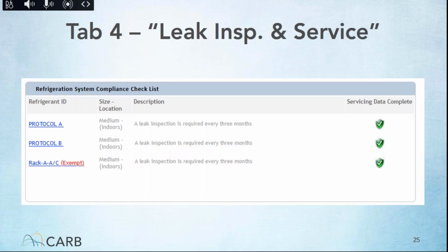So the analysis we take on the leak inspections is, I know my predecessors have tried to do this plus or minus X number of days. The rule doesn't really provide for anything like that. The rule just states 3 months. It doesn't specify what the full integer is. So we look at it more as, if it's 3.5 months, we'll round that down to 3 months, and that's how we're looking at it.